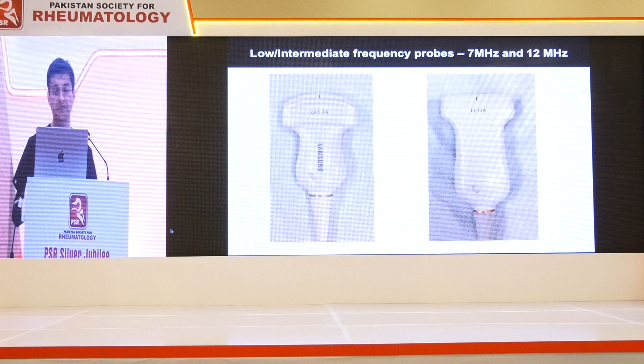So when you start by scanning, make sure you choose the right probe. As I said to you earlier, there are curvilinear probes that often have some sort of a code and will give you some hint as to where the frequencies of this probe are. So this probe will be 1 to 7 megahertz, this will be 3 to 12 megahertz. Every manufacturer has slight variations, but on the probe itself, often will have some sort of code that will let you know what frequency.